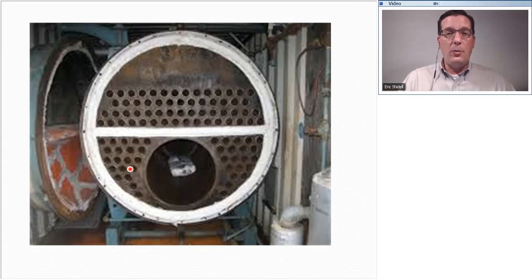When you open this door, you are committed almost 99% of the time to replacing that gasket. And if you don't have one with you, you suddenly created a major problem by opening that door. So be aware, anytime you're going to open the door on a fire tube boiler, you're going to have to replace the rope gasket. So plan ahead. If you don't know what size gasket it takes, open it first, take it out, go get a gasket, and then come back. If it is late in the day and you don't have time to make that trip back and forth, don't open the door. Don't open it just to see what's in there. This is what's in there.